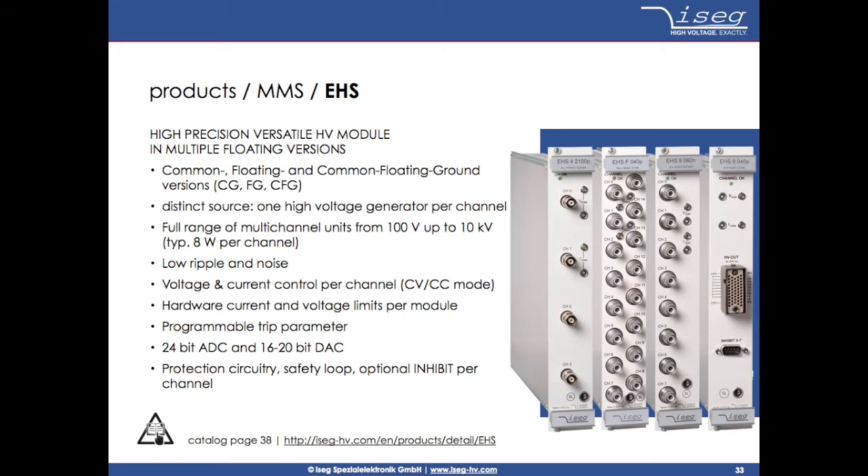The first type of module is called EHS, which is available in 4, 8, 16, and 32 channel versions, with output voltages starting from 100V up to 10kV, with various grounding schemes and different precision levels for different applications, such as silicon detectors, germanium detectors, wire chambers, GEM detectors, and many more.